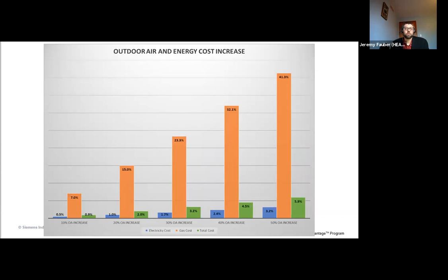All right, so this one looks at the outdoor air energy and how that affects your energy cost. In the blue, we have total impact to electricity. In the orange, we have the impact to the gas. And in the green, we have an impact to the total cost. The orange actually matches the previous slide, where it is the same percentages as what was the blue line, because the only gas usage in this building was for the heating. In other buildings, if you have domestic water heating that's gas, or a kitchen that's got a gas service, these percentages would lower from that peak. But we do see a pretty significant increase in gas energy usage from this.